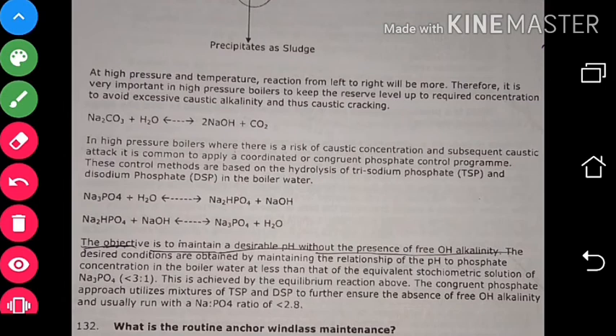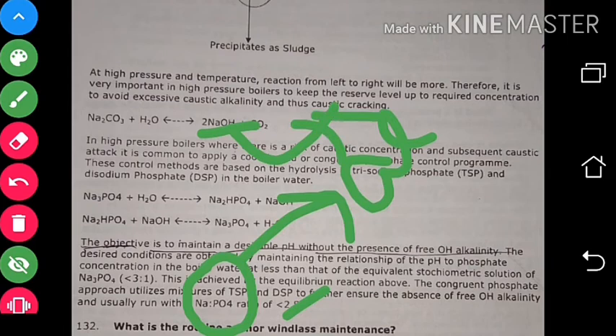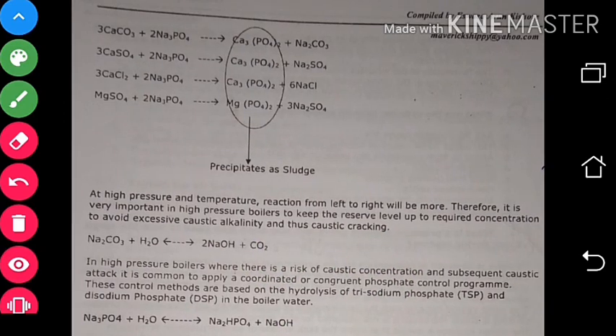At high pressure and temperature, it is very important in a high-pressure boiler to keep the reserve level at the required concentration to avoid excessive caustic alkalinity and thus causing caustic cracking. NaOH at high temperature will cause caustic embrittlement in the boiler. So if phosphate reserve is low it forms scale; if phosphate reserve is high it can form sludge and cause caustic cracking due to NaOH formation.